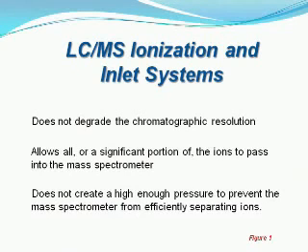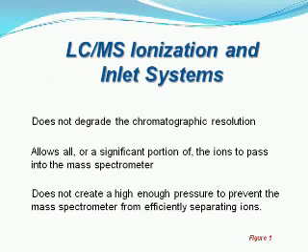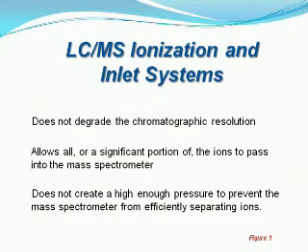So there's a critical requirement on the vacuum system to pump all of that vapor out. How much vapor are we talking about? For one milliliter per minute of flowing acetonitrile, we're talking about a half a liter per minute of acetonitrile vapor at standard temperature and pressure. Of course, an LC-MS interface is not operating at STP — it's operating at reduced pressure and higher temperatures. And therefore, we're talking about literally liters of vapor produced by the HPLC mobile phase, all of which has to be removed by the vacuum system. So there's quite a serious requirement on the part of the vacuum system.